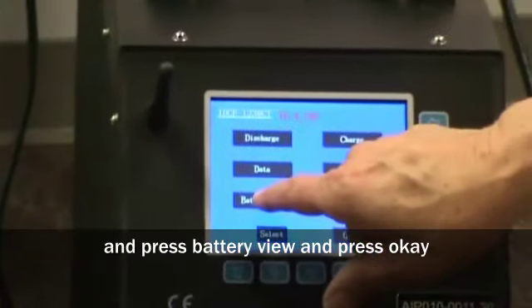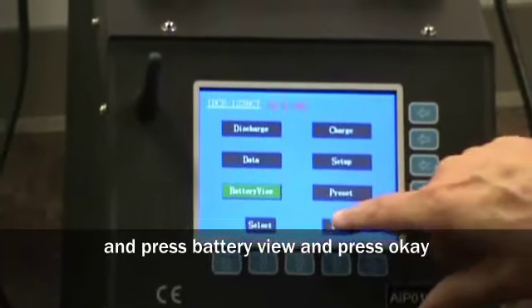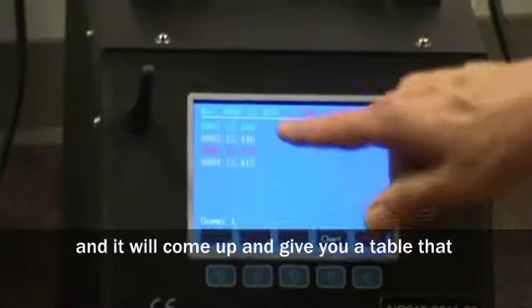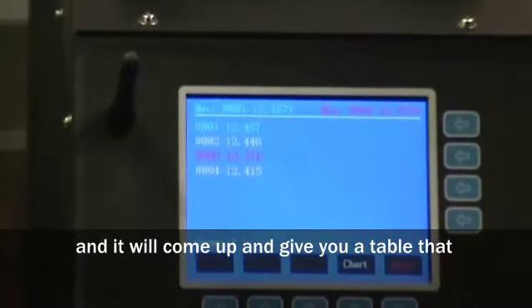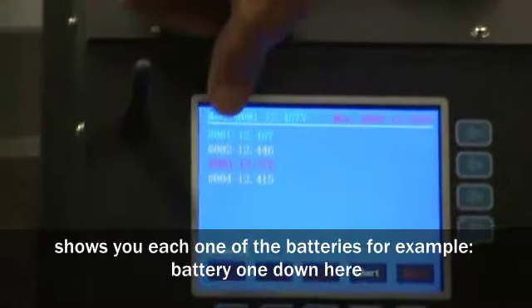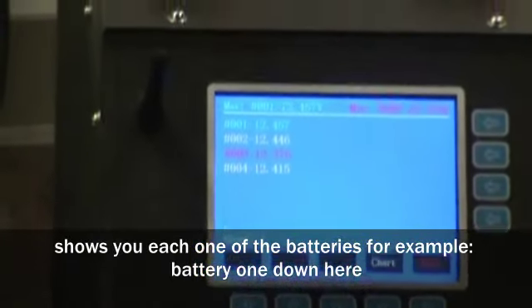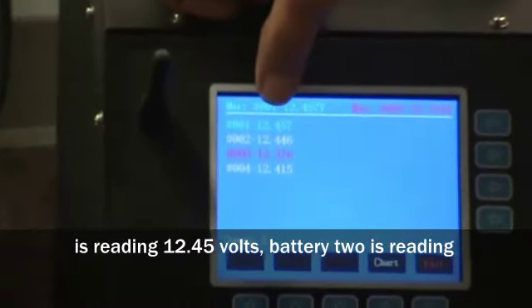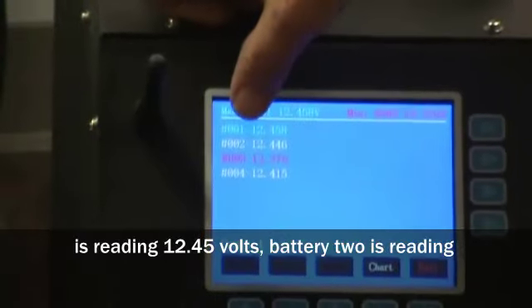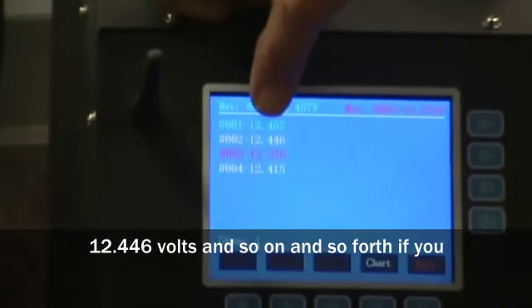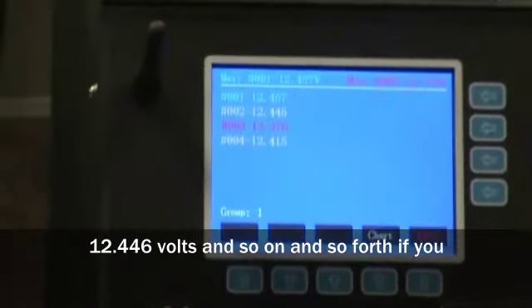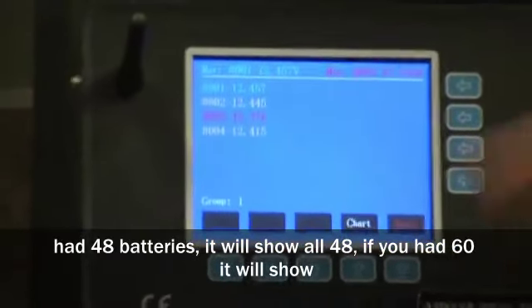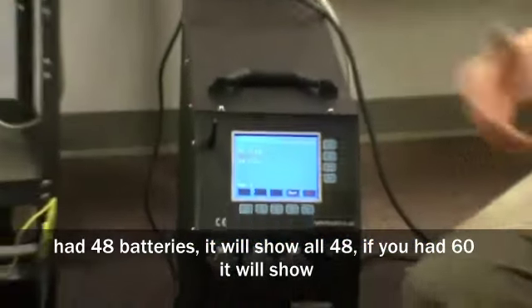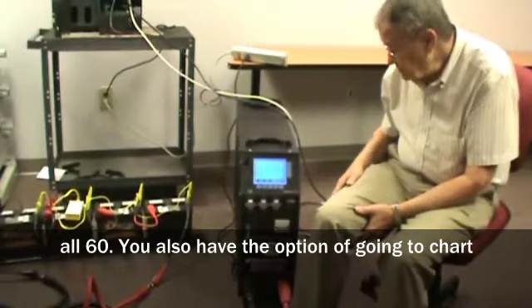Now you can go over and press battery view. You press OK, and it will come up and give you a table that shows you each one of the batteries. For example, battery 1 down here is reading 12.45 volts. Battery 2 is reading 12.446, and so on and so forth. If you had 48 batteries, it would show all 48. If you had 60 batteries, it would show all 60.